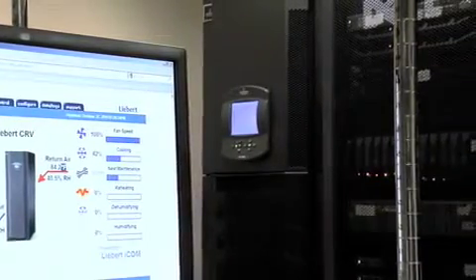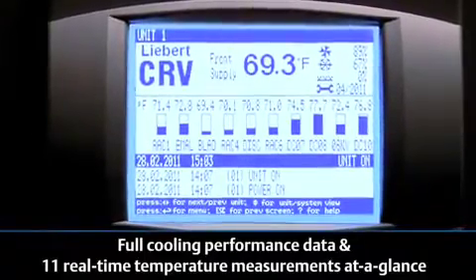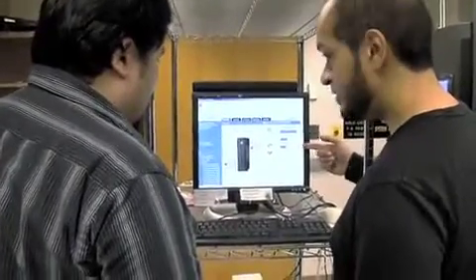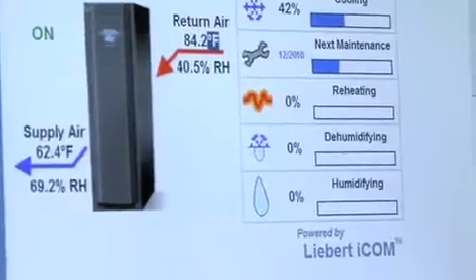Prior to the data center assessment we had a single monitor point on the CRAC unit, and another solution that allowed us to monitor a few locations for temperature and humidity around the server room. The CRV provides a great deal more in terms of monitoring — real-time reporting as well as multiple points of input. The Liebert CRV's ICOM controls have done a very nice job of visualizing what's going on with the unit: the air intake temperatures, the individual rack inlet temperatures — there's a great deal of data available. The remote monitoring helps us deliver continuity of business because our office hours are not 24 hours, but our data operations are. The ability to monitor the CRV and for the CRV to send out alerts is critical to not depending on problem reports to catch actual issues.